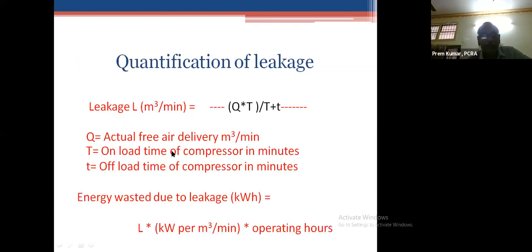It doesn't need big equipment; it needs only a stopwatch. Nowadays, mobiles can do the job. Shut down the equipment usage, start the compressor, and measure the time of loading and unloading. And there's a very simple formula: actual flow into T divided by T plus t.